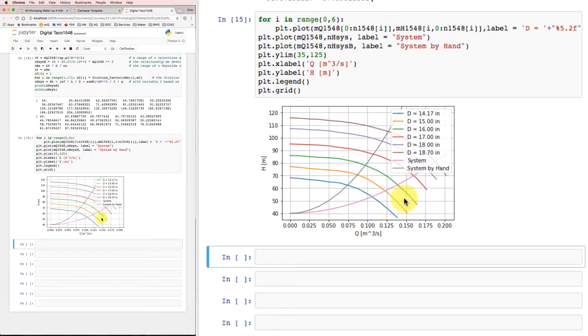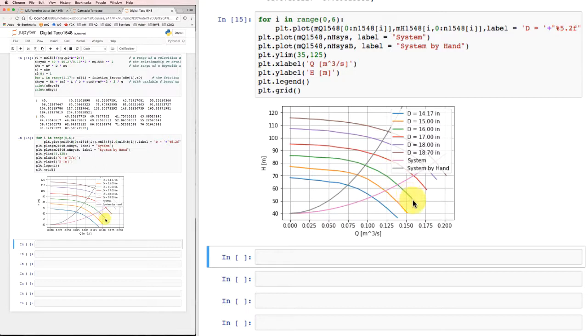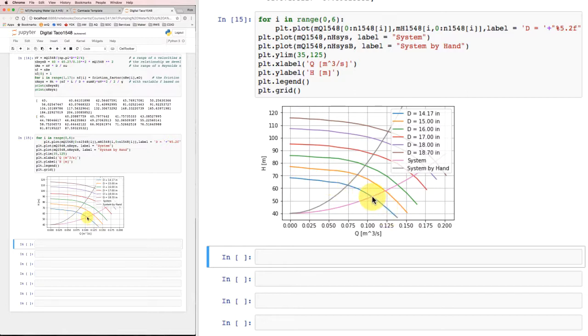So if I had caught this before I'd actually gone to the point of ordering the pump and selecting this 16-inch impeller, I could decide that I can get away now with this 14.17-inch impeller, the smaller impeller, in the same pump and I'd still get more than my required design flow rate of 0.1 cubic meters per second. So that could save me some money and it would probably be a little bit more energy efficient.